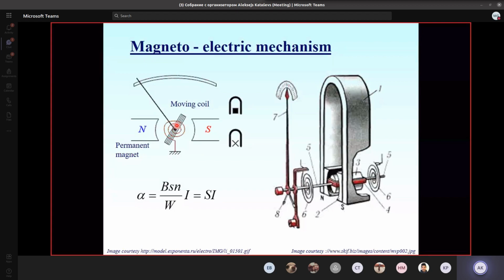But of all the mechanisms, magnetoelectric ones are the most sensitive. They may be extremely sensitive because we may select a magnet with a very high magnetic field, we may make the coil very light with a low moment of inertia, and we may take quite low stiffness springs. Sometimes the magnetoelectric mechanism is used in so-called photogalvanometric measurements, when we don't use an index at all, and we use just a light beam which reflects from a tiny mirror attached to the axis of the system. In this case, the inertia of the system is as small as is possible for a mechanical system, and the sensitivity will be very high because the deflection angle will be very small.